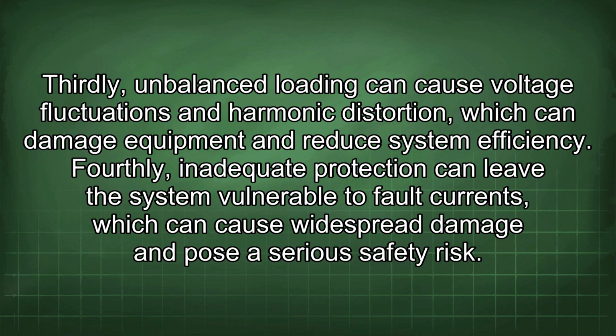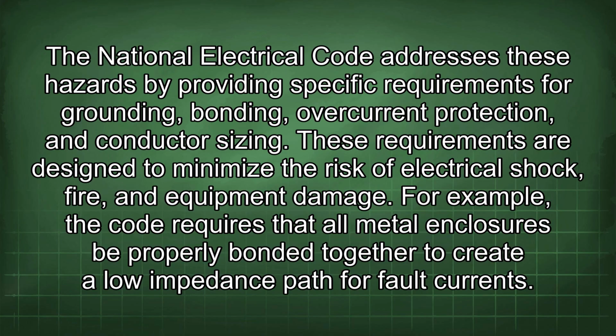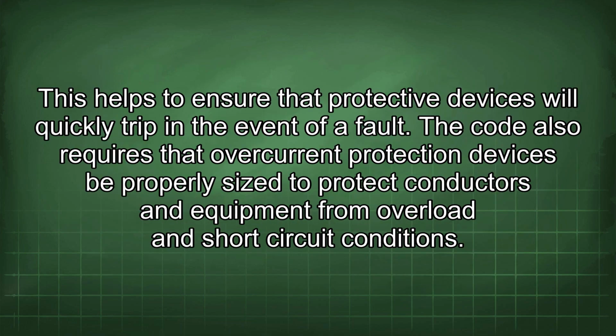Fourthly, inadequate protection can leave the system vulnerable to fault currents, which can cause widespread damage and pose a serious safety risk. The National Electrical Code addresses these hazards by providing specific requirements for grounding, bonding, overcurrent protection, and conductor sizing. These requirements are designed to minimize the risk of electrical shock, fire, and equipment damage. For example, the code requires that all metal enclosures be properly bonded together to create a low impedance path for fault currents. This helps to ensure that protective devices will quickly trip in the event of a fault.